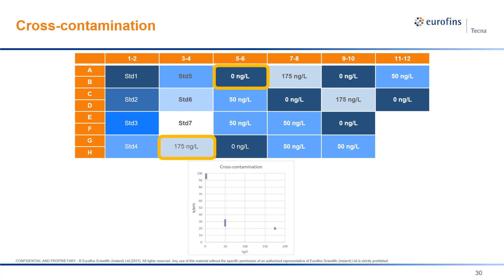I went for a cross-contamination investigation, loading first a highly contaminated material with concentration close to the upper concentration level of the curve, followed by a blank milk, and then some samples with intermediate contamination. If the pin were not adequately cleaned I would have noticed some carryover — some over-contamination in the well following the highly contaminated sample. As this did not happen over repeated tests, I was confident there was no carryover issue.